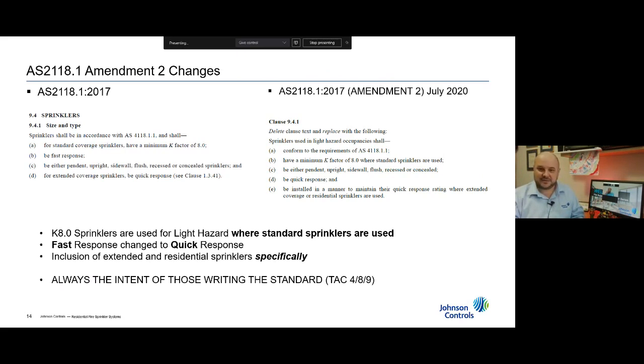If you have consultants or fire engineers that are concerned about the use of flush sprinklers, for example, we can use them in accordance with this standard and this clause. It was never really meant to exclude the use of them, just the wording wasn't quite right. So that's been changed to quick response, which is nice. And like I said, we've included the residential sprinklers specifically as being allowed. While this is not referenced in the BCA, it's really important that this was always the intent. This isn't a change of intent from the old standard. It was always the intent by those writing this standard.